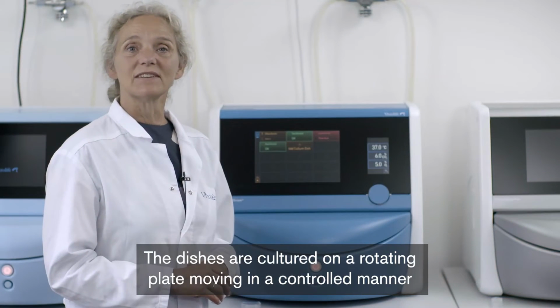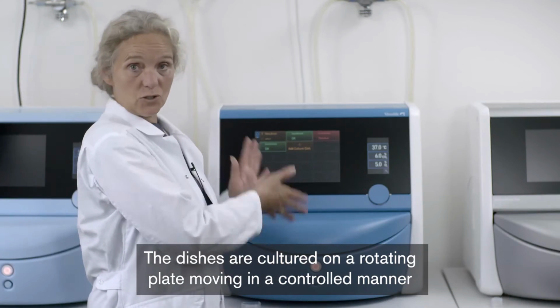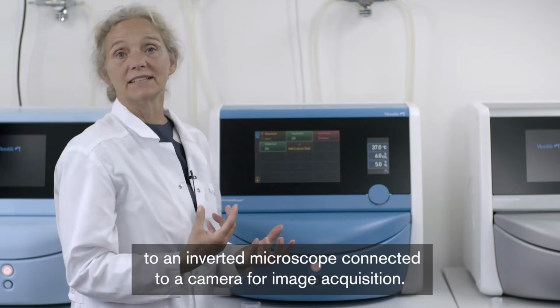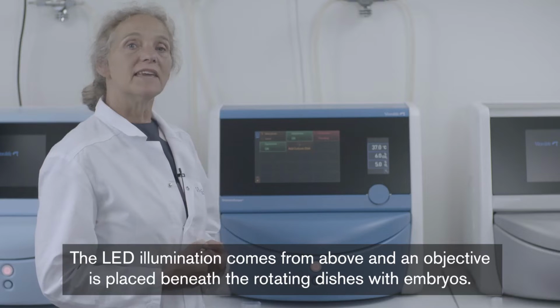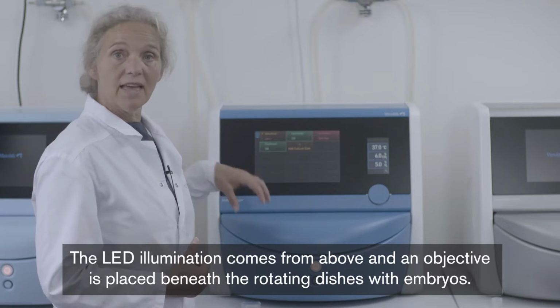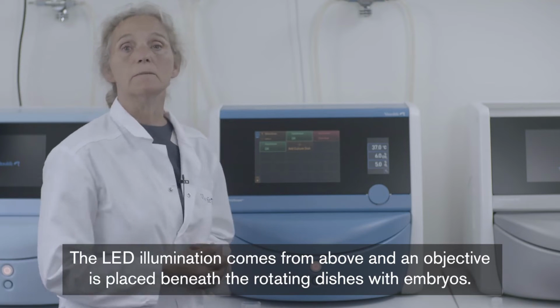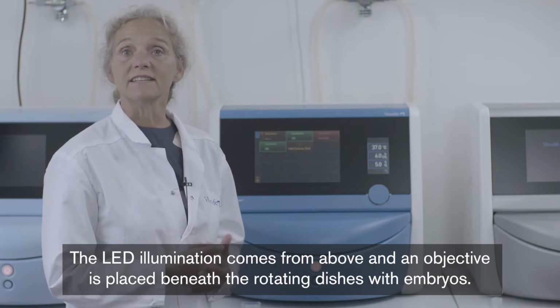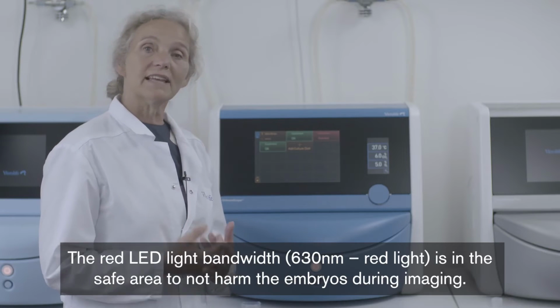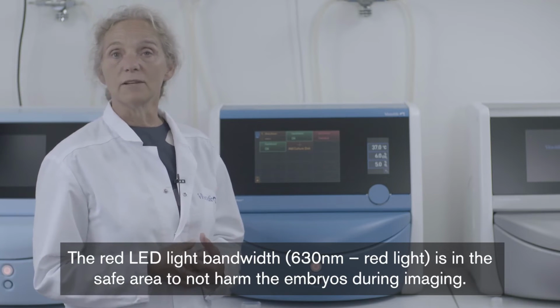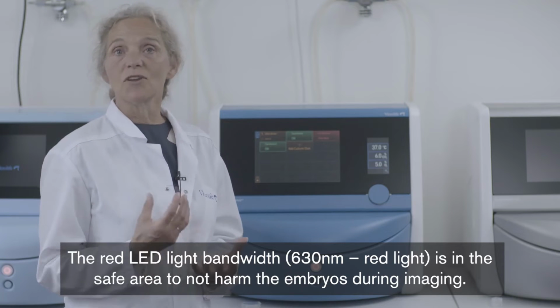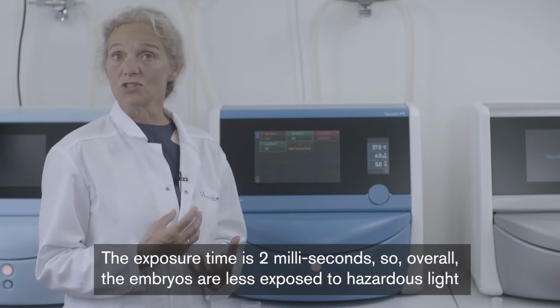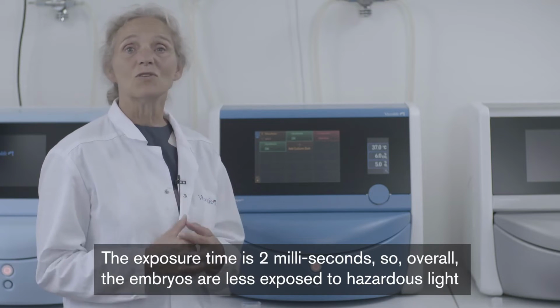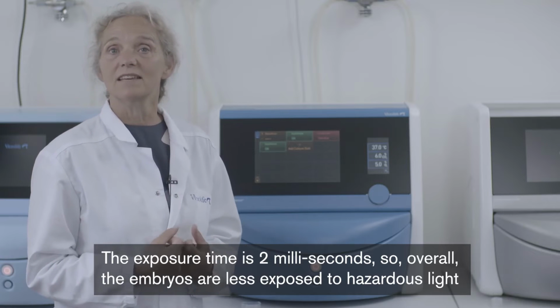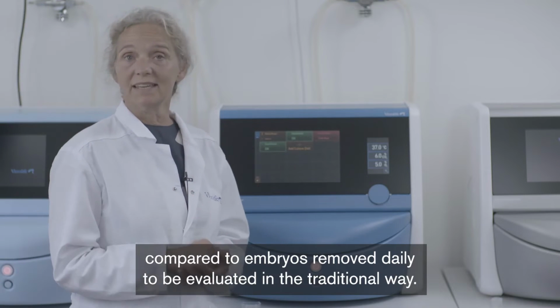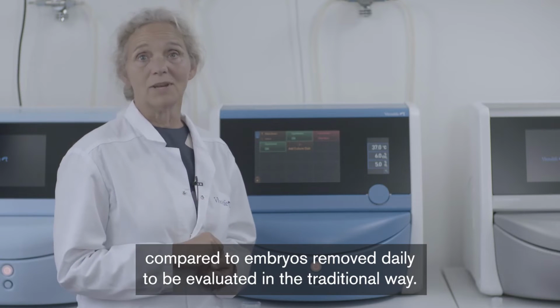The dishes are cultured on a rotating plate, moving in a controlled manner to an inverted microscope connected to a camera for image acquisition. The LED illumination comes from above, and an objective is placed beneath the rotating dishes with embryos. The red LED light, 630 nanometer red light, is in the safe area to not harm the embryos during imaging. The exposure time is 2 milliseconds, so overall the embryos are less exposed to light compared to embryos removed daily to be evaluated in the traditional way.